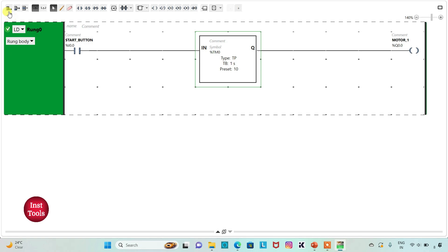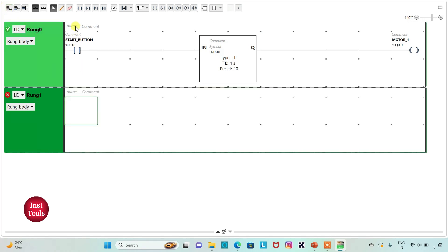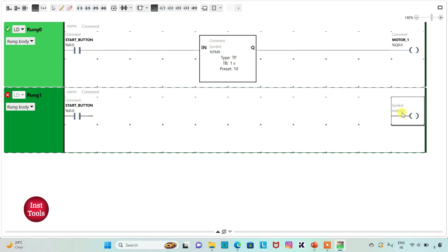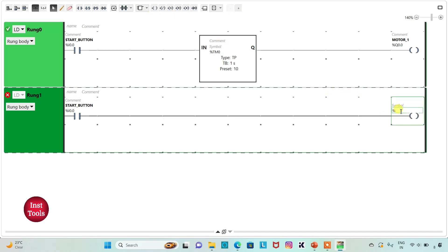I will add a new rung for the second stage motor. I will insert a normally open contact and assign address I0.0 — same as the start button. Then I will insert a coil and assign address Q0.1 to it, adding the symbol 'motor 2'. Motor 2 should be on after 15 seconds — that is, when motor 1 will be off and then after a 5-second delay, motor 2 will be on.